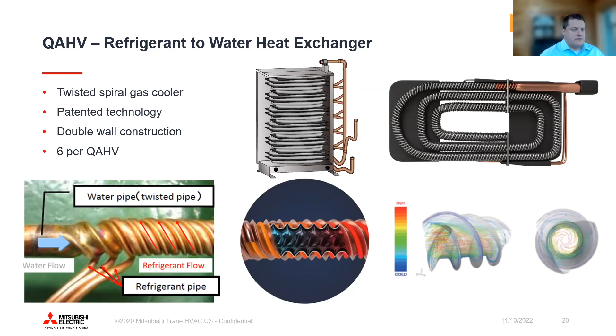This is just going to show you a little bit. I think sometimes people get a little bit timid when it comes to CO2. It's actually a very common refrigerant we use in the US all the time. But the one thing I wanted to show here is that we do use the same vapor injection that we have for our HyperHeat VRF products. So basically, it allows us to bring in mixed phase gas to cool the compressor down, allows it to run harder at lower temperatures without damaging the equipment.